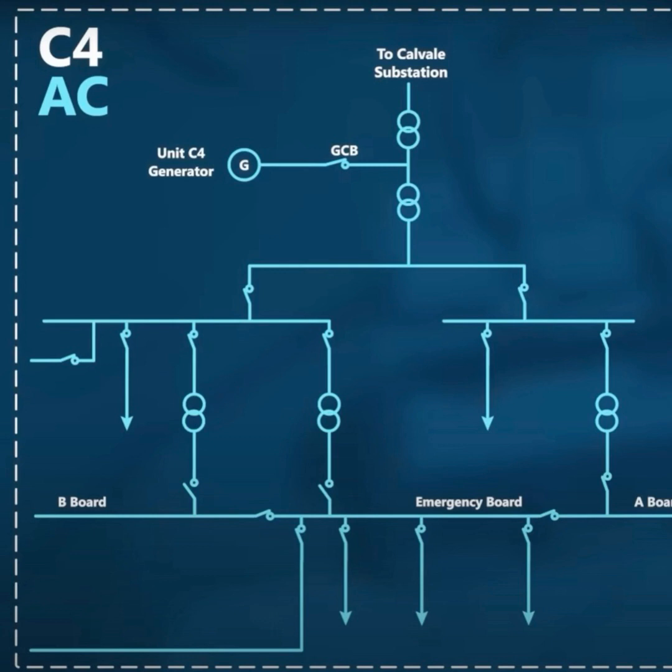Unfortunately, I don't have photos of the switch room. However, I've been in enough switch rooms in the last 30 years to make an educated guess about why they didn't operate the changeover switch. For traditional LV and MV switchboards in the days before SCADA systems, it was quite popular to draw key parts of the electrical single line diagram, or SLD, overlaid on the front of the switchboard. An SLD shows which components connect to what electrically, from transformers to circuit breakers, transfer switches, and destination loads. You can still order switchboards with an SLD mimic printed on the front panel.